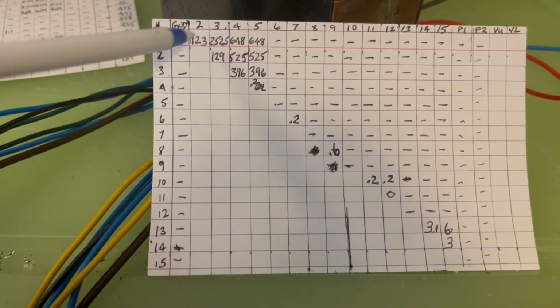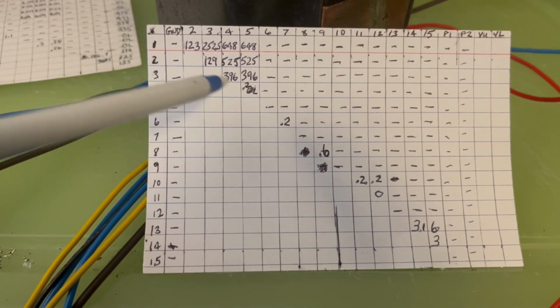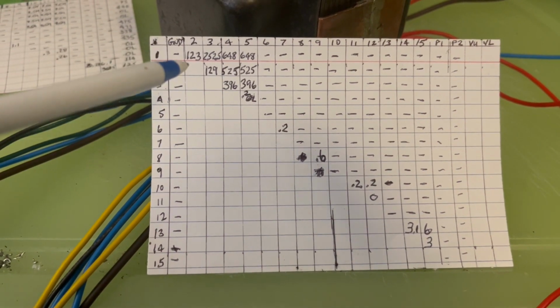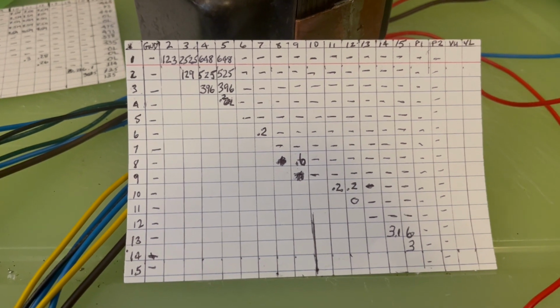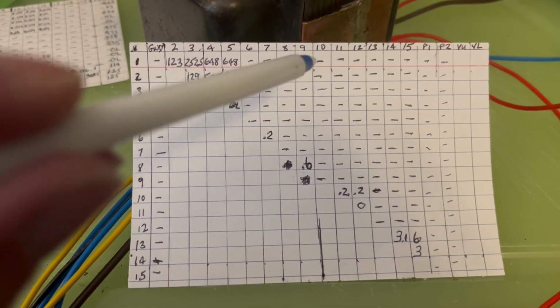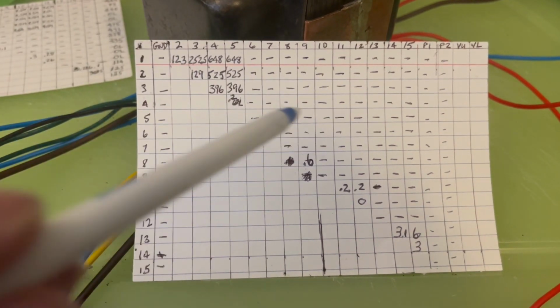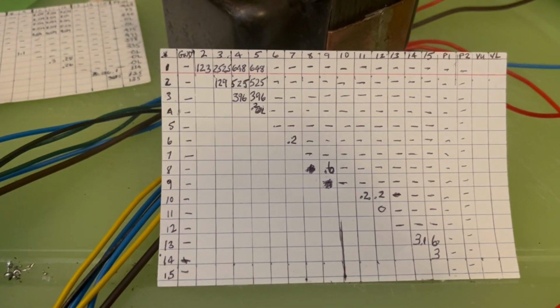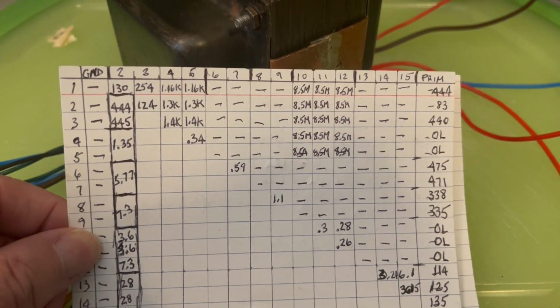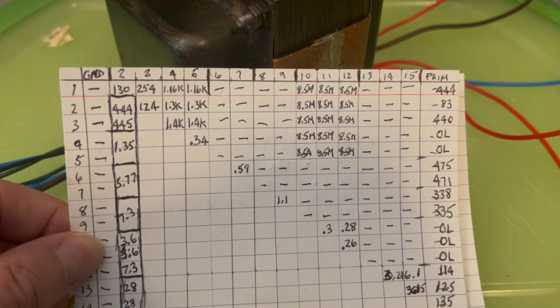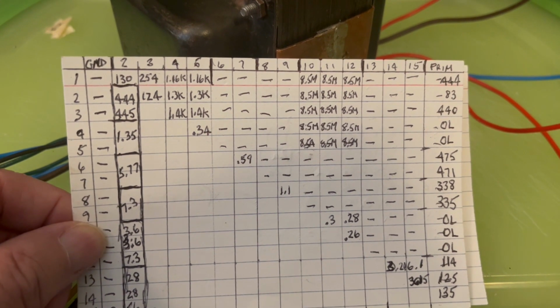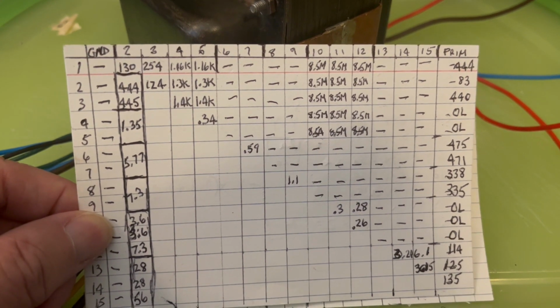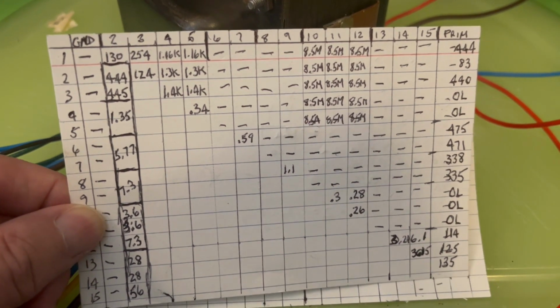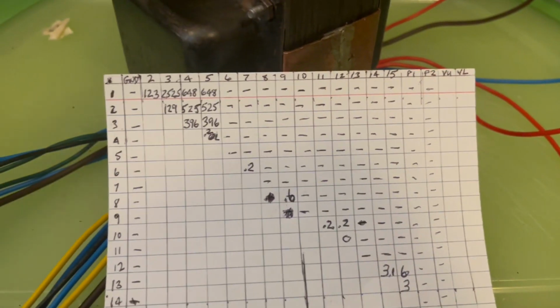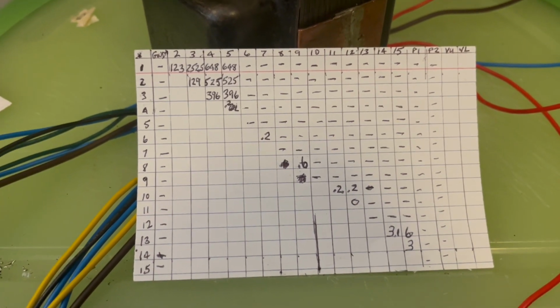The cluster that you see up here is the high voltage coil. The thing that really stands out that's different is that 10, 11, and 12 are no longer shorted with this coil. If you look at the original measurements that I had, that's what the problem was. There I'm showing 8.5 megaohms, but it was really 1.4 kiloohms by the time all was said and done. So I'm a little bit happier with the way this turned out.